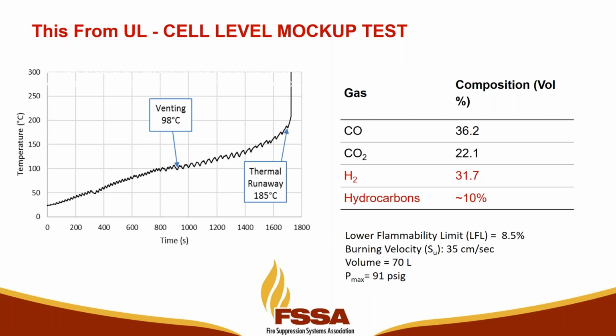Because what they do is purposely drive it into thermal runaway. But beyond that, do the explosion study - understand what the container design is and what you can vent reasonably based on the failure modes to get those gases out. It may need to be a deflagration vent if it's a very small container.